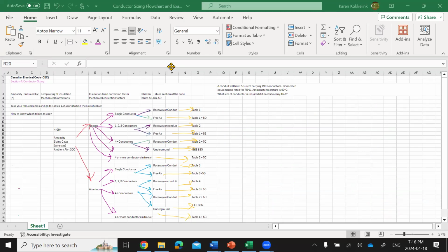So what you end up doing is, let's say you have like 45 amps that you have to supply, but it's really, really hot. And then it's mounted kind of weird, like let's say there's 20 conductors, then you're actually going to have to choose a size from the size table much greater than 45, that'll handle more than 45 amps, like, I don't know, 70 amps, 60 amps, whatever, depending on the example.